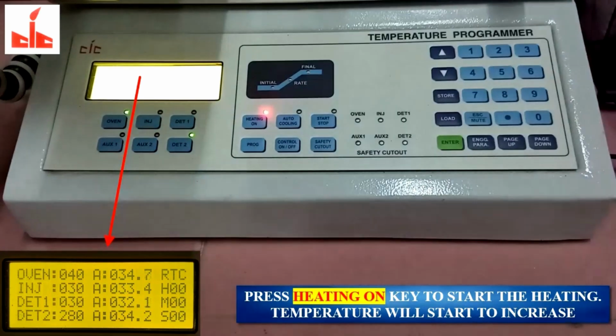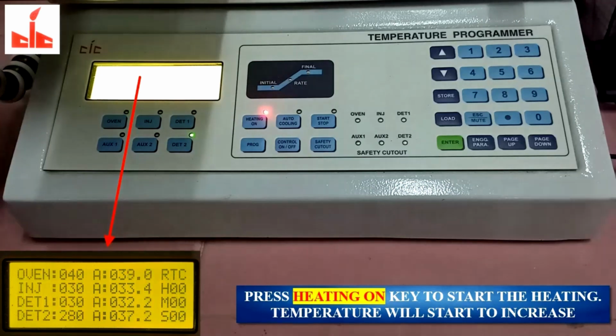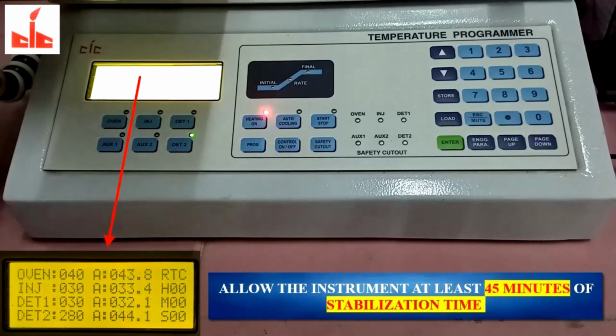Press heating on key, to start the heating. Temperature will start to increase and can be seen on display. Allow the instrument at least 45 minutes of stabilization time.